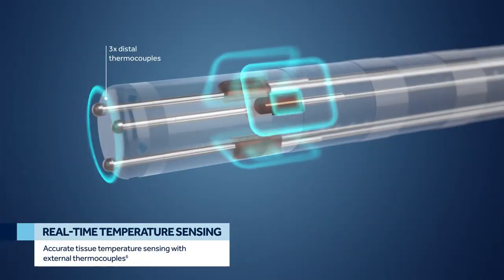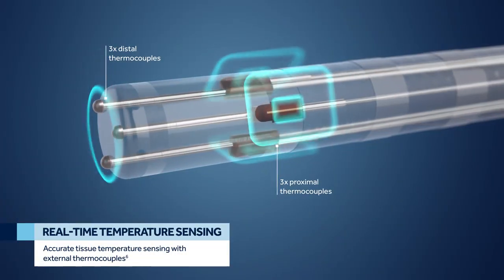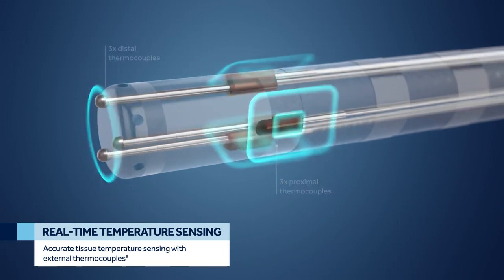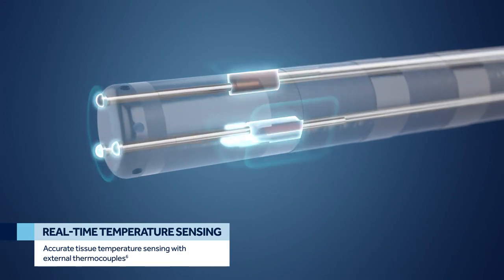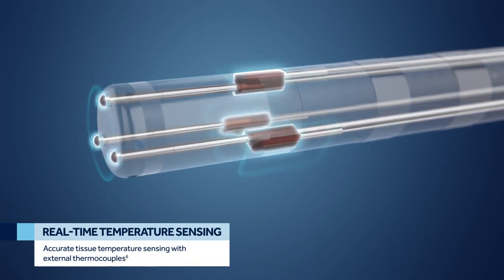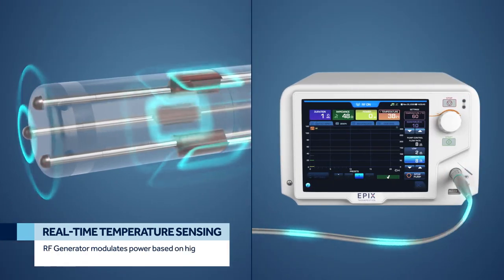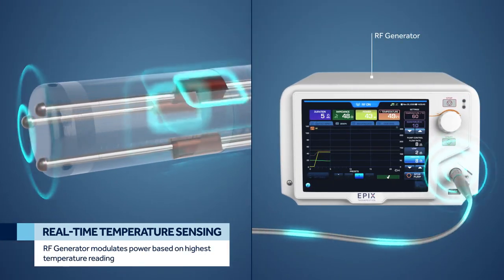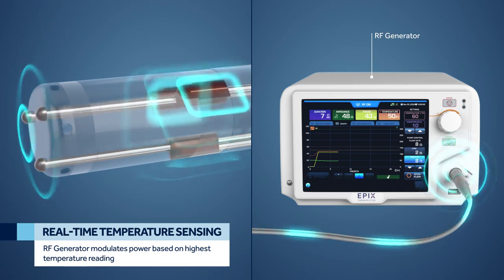The Diamond Tip ablation system automatically adjusts power to maintain therapeutic ablation temperature in real-time. Six external thermocouples measure tissue surface temperature every 20 milliseconds. The RF generator then modulates power based on the highest temperature reading to maintain target temperature during ablation.